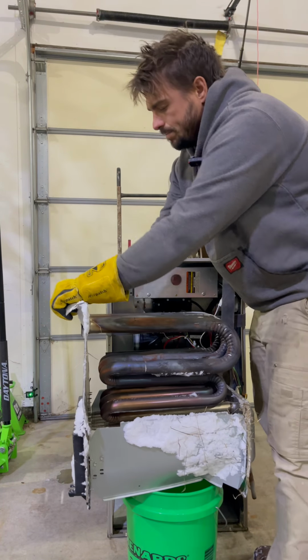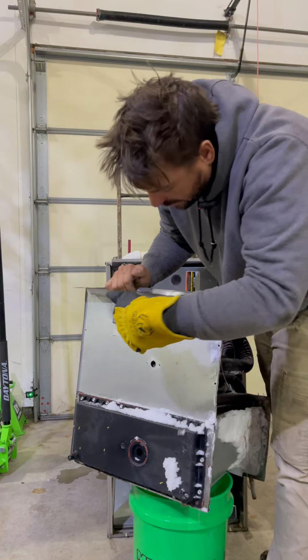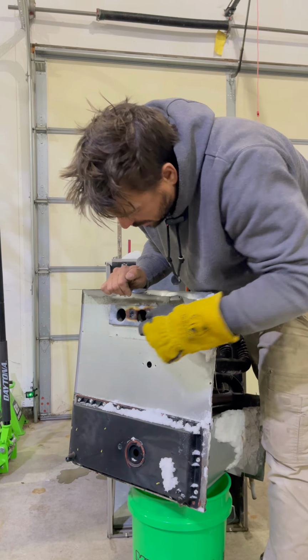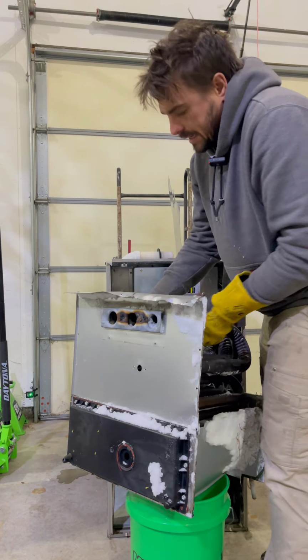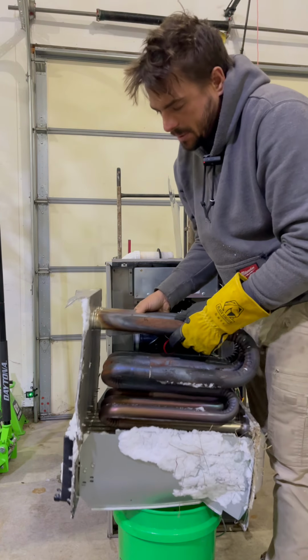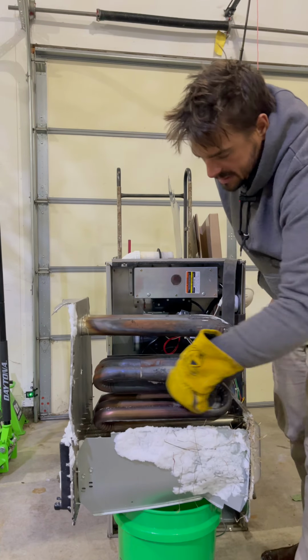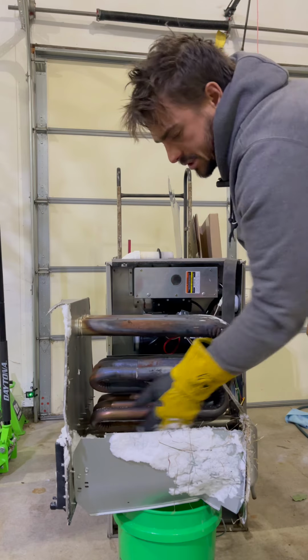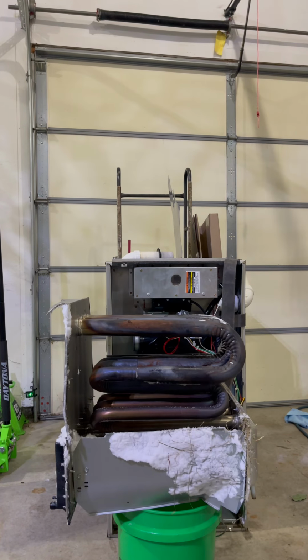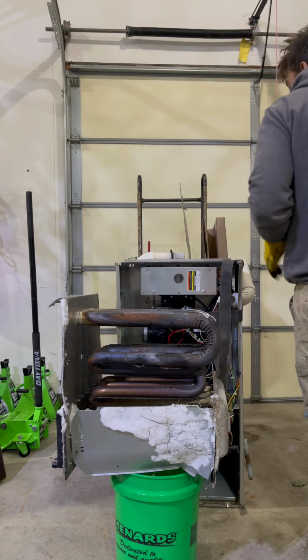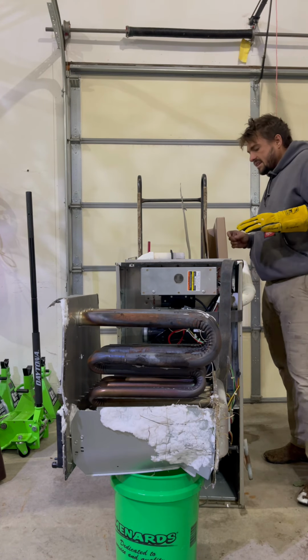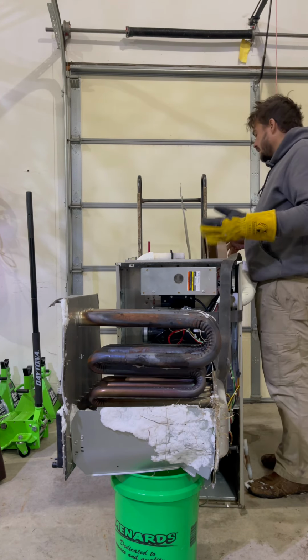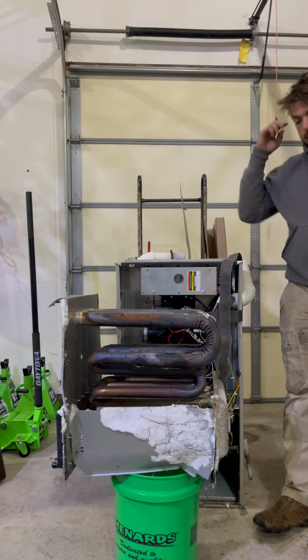There are 2 heat exchangers put together here. When the unit runs, you have flame going down these tubes - you can see this one was all charred. Flame goes down through these big tubes, which we call the primary heat exchanger. Then the secondary heat exchanger is here - you can see there are little tubes. On Carrier and ICP units, the secondary heat exchanger is actually thin channels, which is why they plug up. I don't have one in front of me, but I'm taking one out later today.